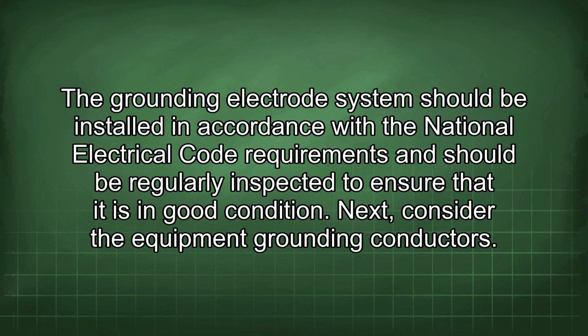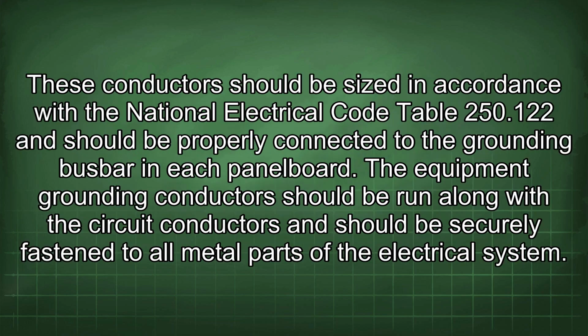Next, consider the equipment grounding conductors. These conductors should be sized in accordance with the National Electrical Code Table 250.122 and should be properly connected to the grounding busbar in each panel board. The equipment grounding conductor should be run along with the circuit conductors and should be securely fastened to all metal parts of the electrical system.